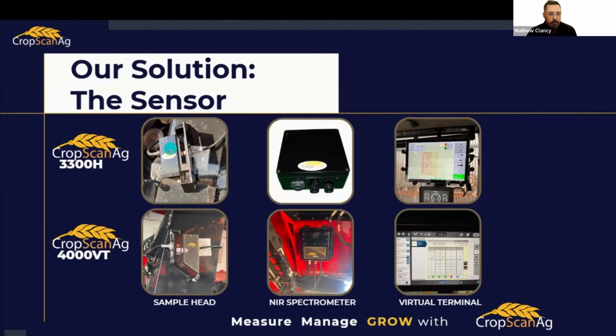The only way we can manage the signal throughput of the grain is by physically moving the probe. When you go to the silo, they have an automated probe adjustment mechanism, and the probe will drive itself in when it's doing canola. It'll drive itself out a little bit when you're doing wheat, and out further for something like a fava bean. We have a physical manual probe position. Generally we'll be starting in canola, so push that probe all the way in so it's hard up against the stop. I actually put pressure with my hand and tighten the lock nut. That makes sure you get it all the way in, and then that 7 millimeter gap manages the signal throughput and keeps it constant.